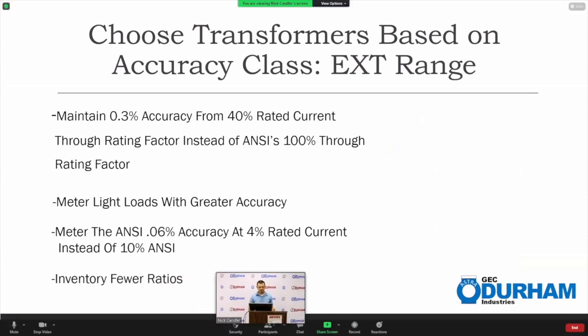So extended range transformers: this is 0.3 accurate from 40% of the rated current, not the nameplate ratio, up through the rating factor. It actually goes down to 4%. It meters lighter loads with greater accuracy. And that 0.6 accuracy starts way down at 4% of the current instead of the 10% of your standard transformer. So by doing that, you're able to cover a much larger range of CTs. You can stock fewer CTs. There's some money savings there.